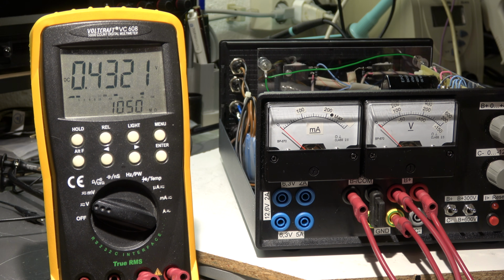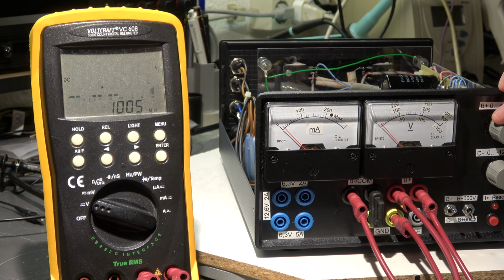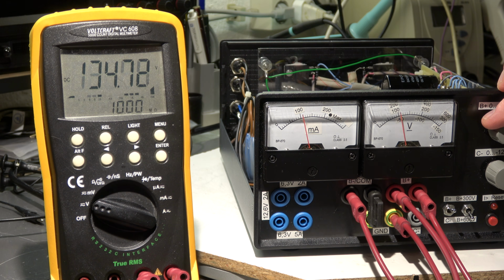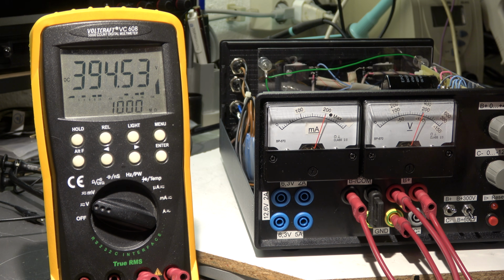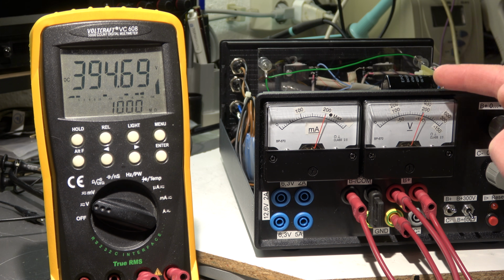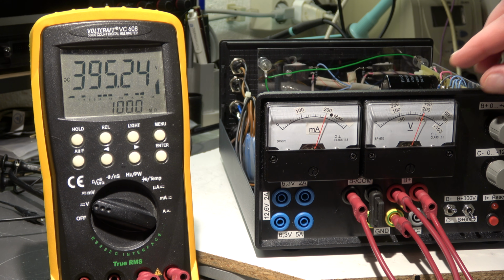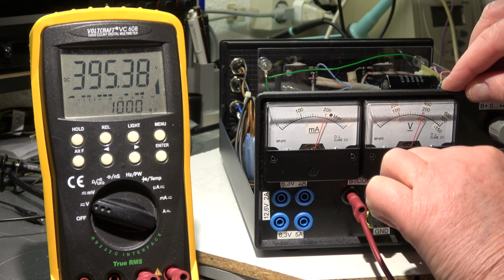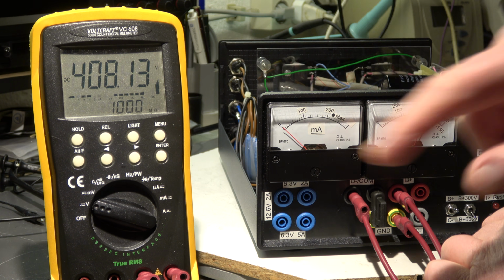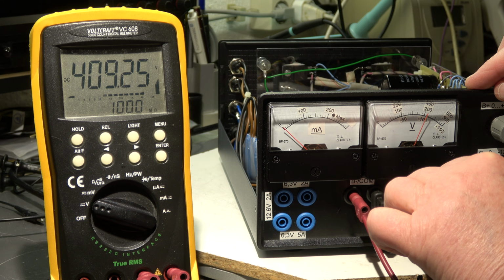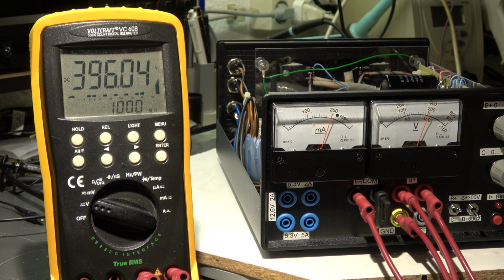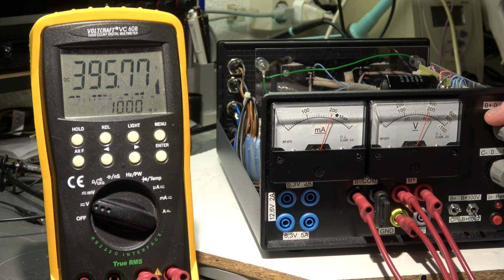We see 600 volt. Okay, that's the limit, 395. Here we have some problems because this is the limit of the power transformer, and when I reduce the load, I plug it off, you see the voltage rises, goes up and goes down. So this is not typical for the voltage stabilization.